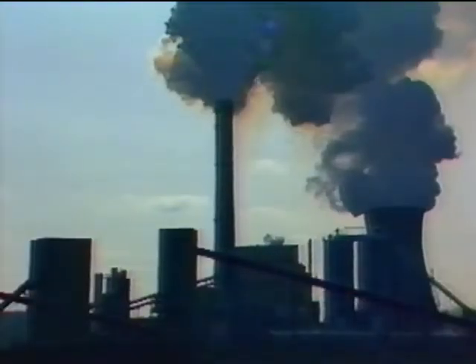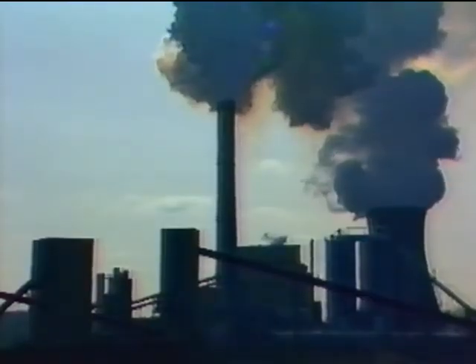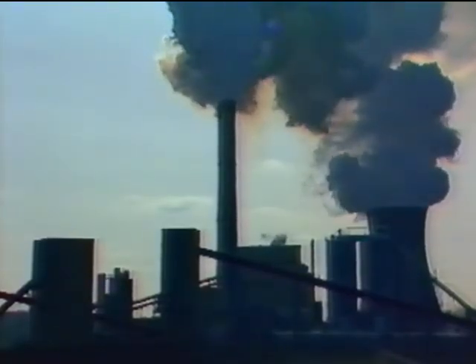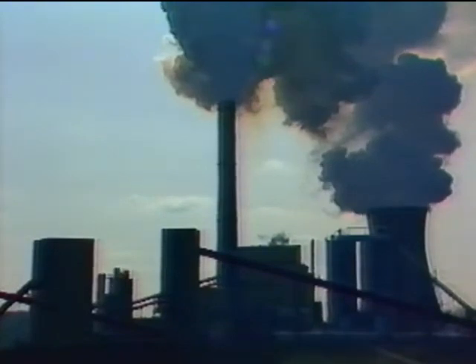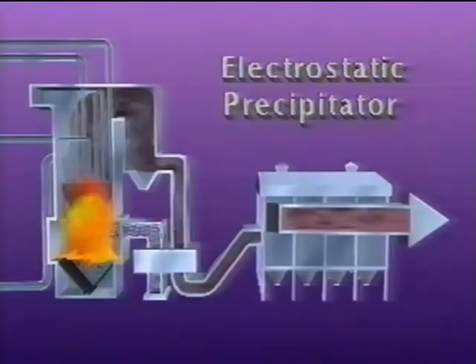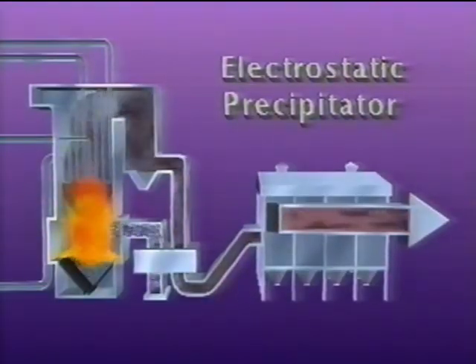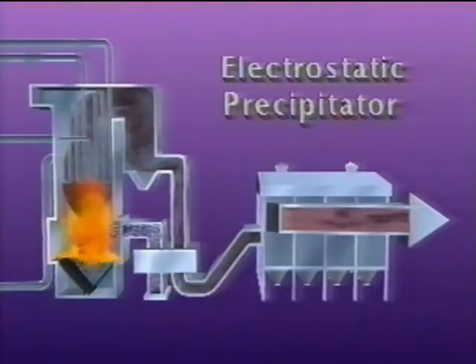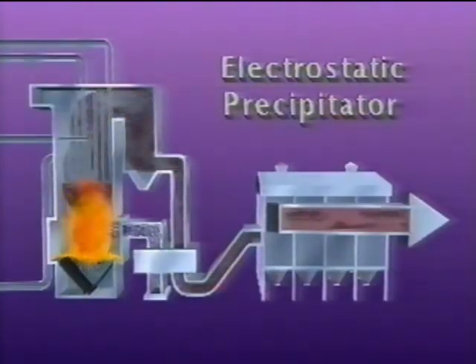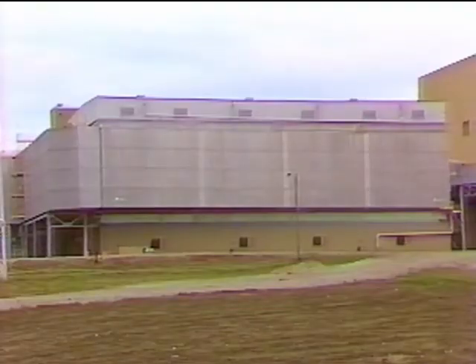To limit air pollution often associated with coal burning, two state-of-the-art pollution control processes work together at Zimmer to deal with the exiting flue gases. Equipment called an electrostatic precipitator, which works much like a giant electronic air cleaner, collects 99.8% of the fly ash particles from the flue gas before they enter the flue gas desulfurization or scrubber system. About 60 tons per hour of fly ash is removed at full load, depending on the coal being burned.